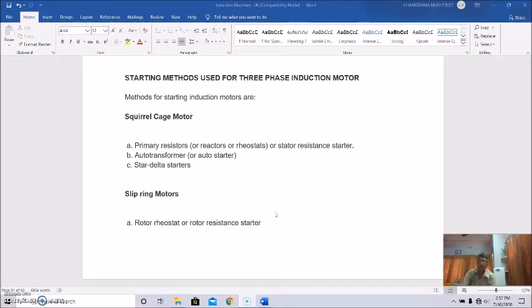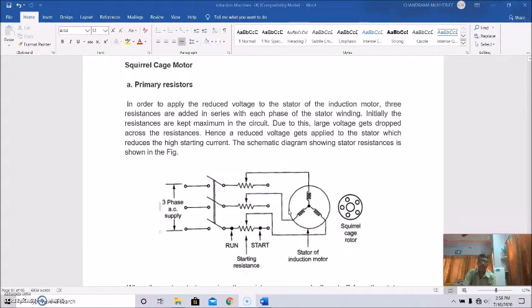Okay, so for squirrel cage, that is primary resistor or resistance starter, or primary reactors or rheostat starter. Secondly, auto transformer starting, and third is star delta starter. And for slip ring motors, it is the rotor resistance or rotor rheostat starter. So there is a basic difference between these two resistor starters. Primary resistor means it is the stator resistance starter, and here it is the rotor resistance starter for slip ring motors. Okay. Let us start with primary resistors.